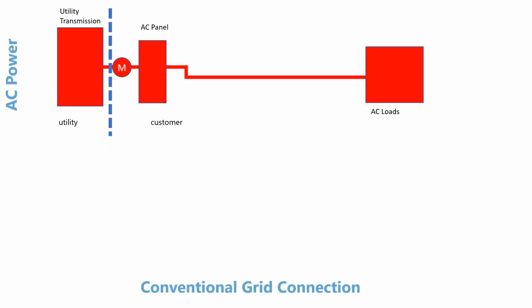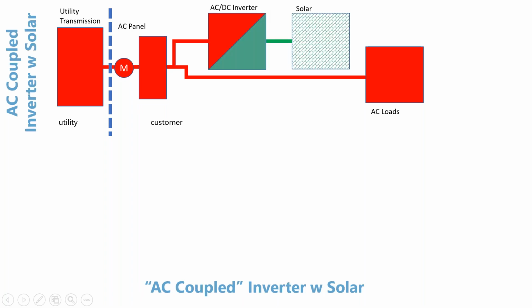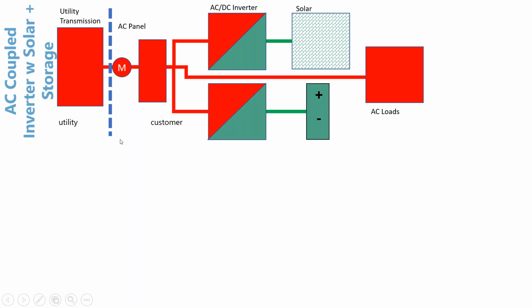I'm going to keep this relatively high level and show you how a traditional home is powered. A traditional home has an AC utility connection, a meter, and an AC panel that then serves the AC loads in a house. When you add solar onto a conventional house, you're placing a DC source, the solar panel, on the roof. You have to pass it through a DC to AC inverter to make AC power to then feed into your panel and AC loads. When you add battery storage into that same system, you have to add your batteries and a separate inverter. So now you have two inverters in order to take the power that's generated from the solar, convert it to AC, direct it to an inverter to generate DC, store it as DC, and then again pull it back out. And you can probably appreciate the inefficiencies that are associated with that.